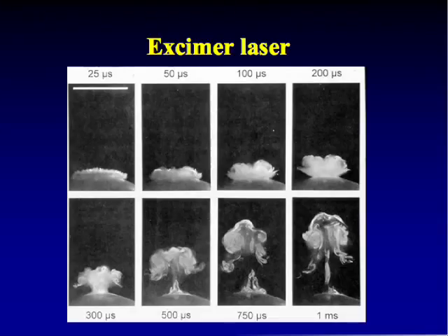And so this was one of the early excimer lasers when they were thinking of using it more like a knife, and you get this nice, beautiful mushroom cloud of sublimated material disappearing off into space. It looks beautiful, but of course if you're trying to treat a big patch with the excimer laser, that's going to cause an irregular ablation and diffraction and distortion and glare and all those things. So you need a fan to blow all that stuff out of the way before the next pulse comes in. Otherwise, you'll get bad pulses.